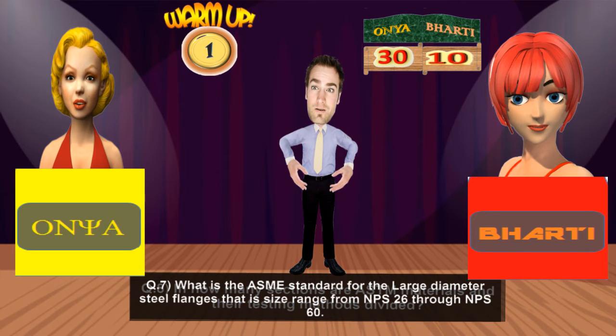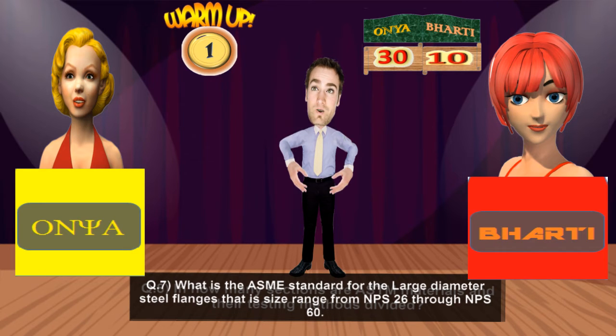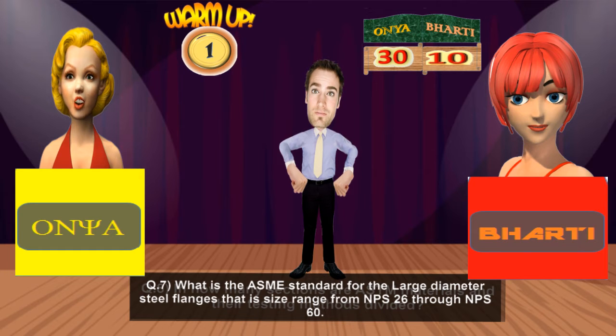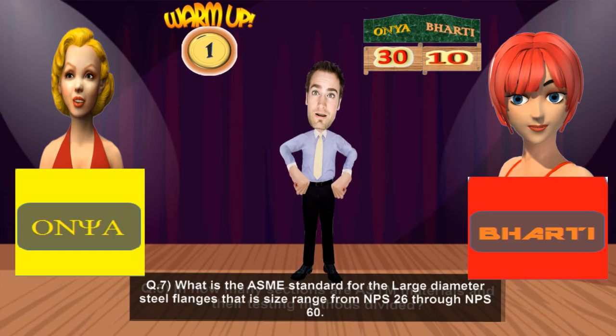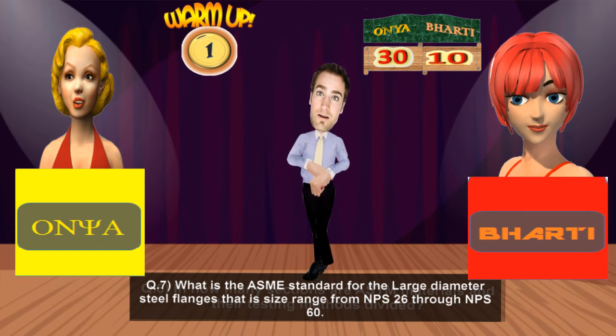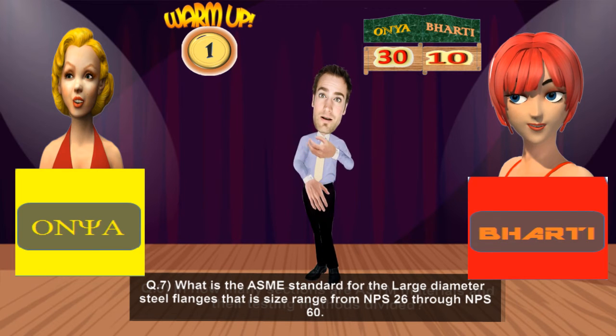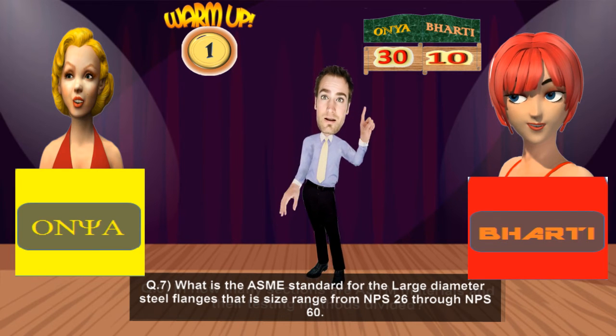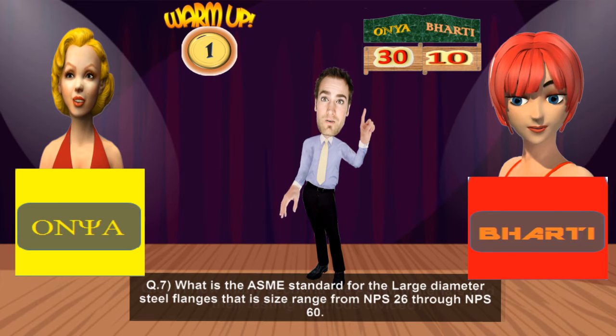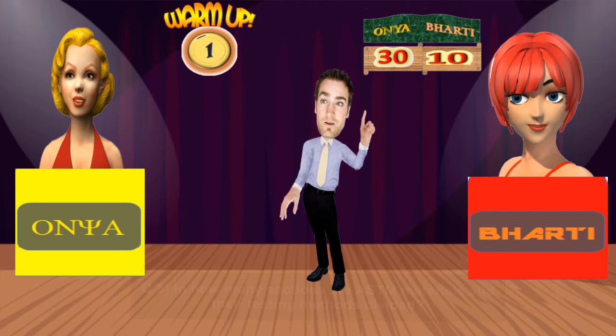Next question for Ms. Onya: What is the ASME standard for large diameter steel flanges, that is size range from NPS 26 inches through NPS 60 inches? Ms. Onya answers ASME B16.5, but that's wrong. The actual answer is ASME B16.47. ASME B16.5 is for pipe flanges and flange fittings less than NPS 26 inch size. Time to catch up, Ms. Bharti.